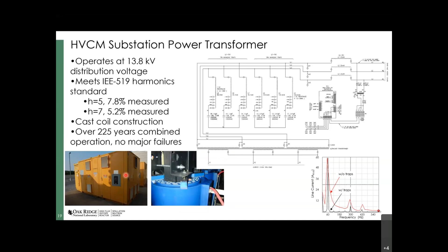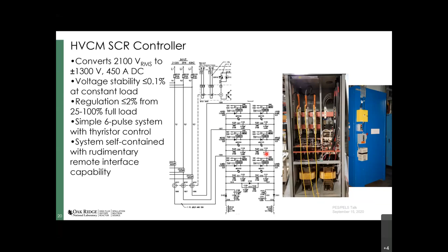The next thing, of course, is we take that 2100 volts that comes out of that unit and feed it into an SCR controller. It's a 6-pulse system. This is a schematic of the basic system itself. Power comes in through here. We have CTs and PTs to monitor the line levels, and then we run through the 6 thyristors. We can generate up to 450 amps at plus or minus 1300 volts with this system. The regulation is less than 2% from 25 to 100% of full load. It had some rudimentary control interfaces, but we've since improved upon that in the subsequent years. So this is what it looks like in the business end, if you will.